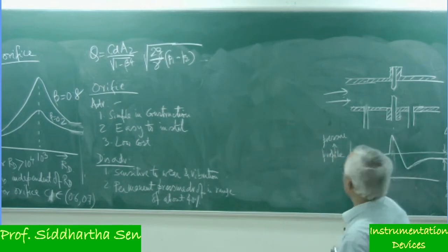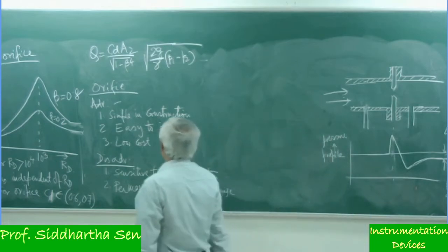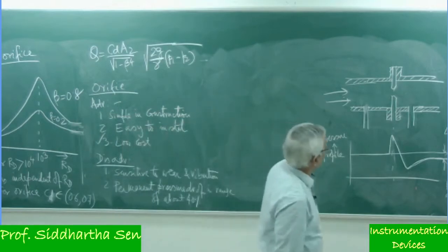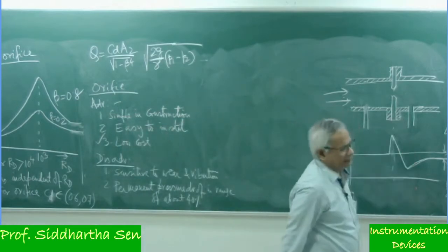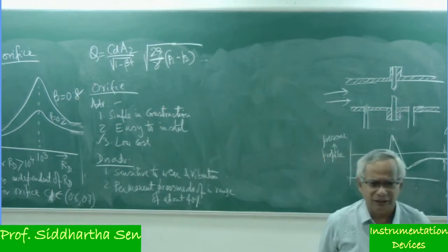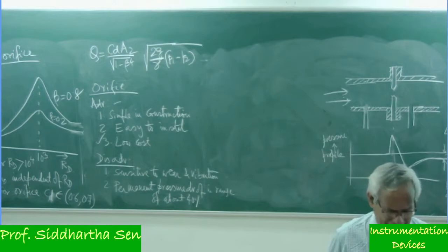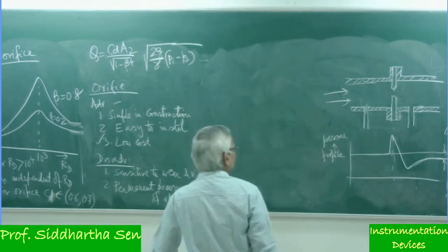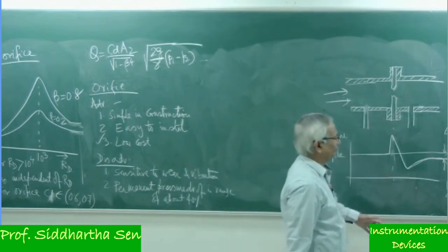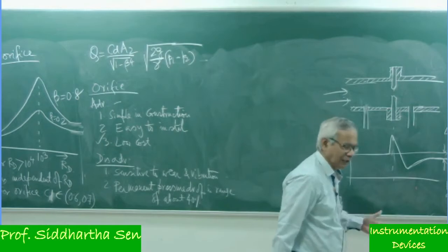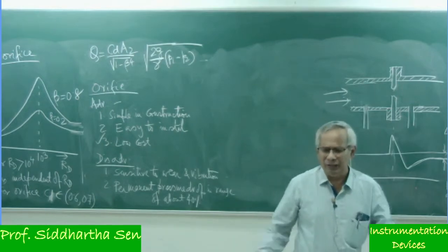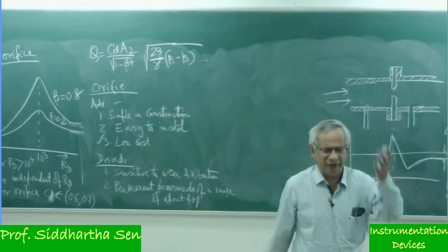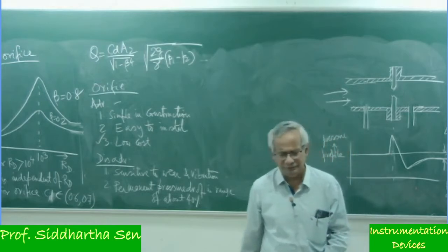So obviously we say that the orifice is low cost because it is simple to use. You can construct it and put it in like this easily. But the major issue is that in the long run you are sacrificing, because the cost will be more, since you are not able to pump the water to that high level. As a result, we will have to increase the pump size, and that cost will be another problem of this one.